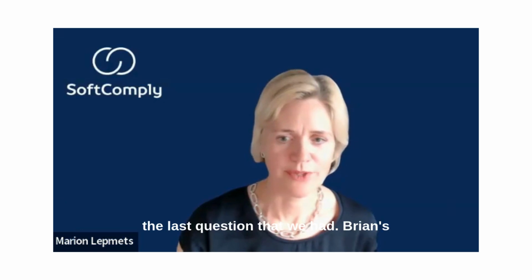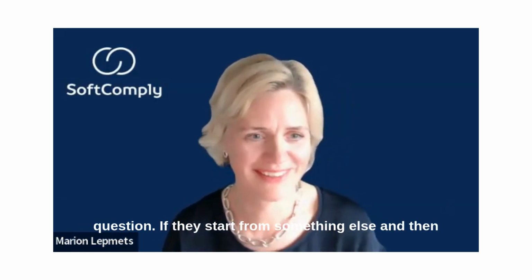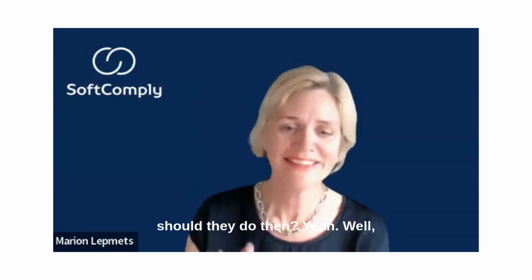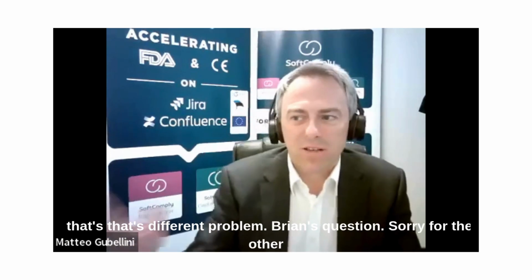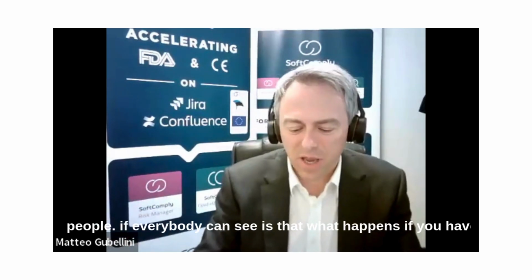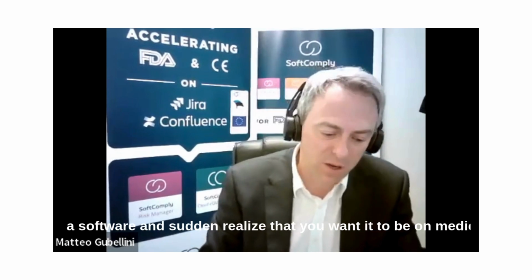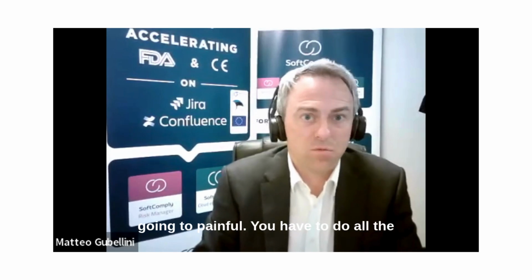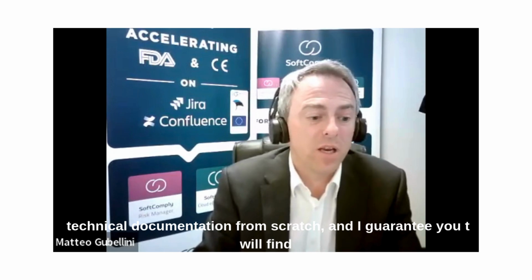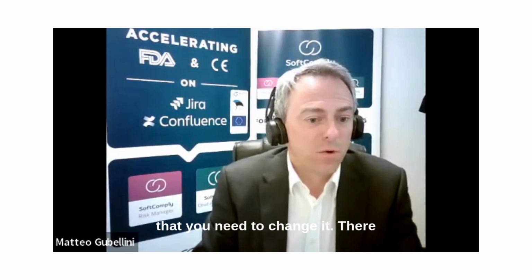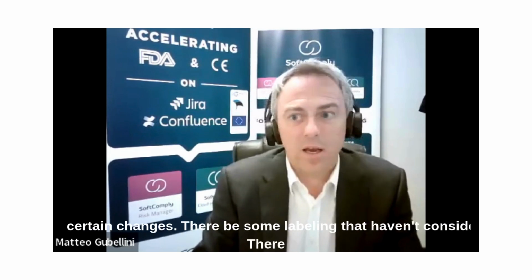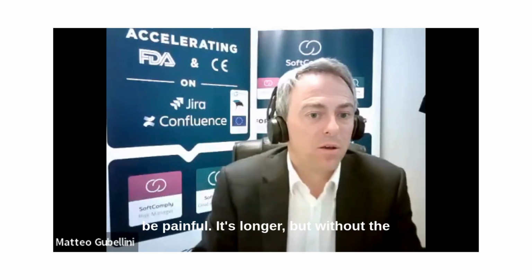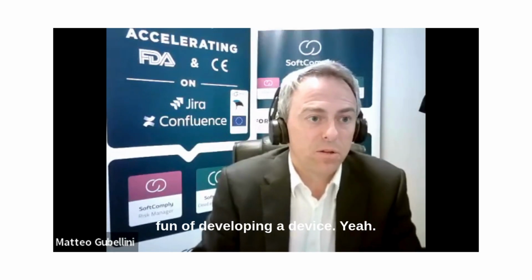I think you answered the last question that we had, Brian's question. If they start from something else and then realize that it's a medical device that they want to do, what should they do then? Well, that's a different problem. Brian's question, for the other people, is what happens if you have software and all of a sudden realize that you want it to become a medical device, or it should have been a medical device. It's going to be painful. You have to do all the technical documentation from scratch, and I guarantee you that you will find that you need to change it. There will be something from the risk assessment that will highlight certain changes. There will be some labeling that you haven't considered. So it's going to be painful, longer, but without the fun of developing a new device.